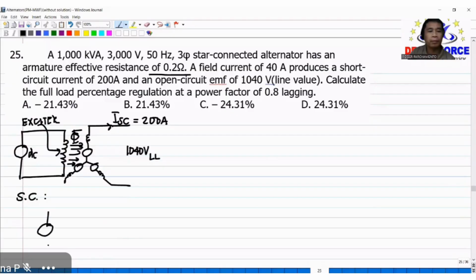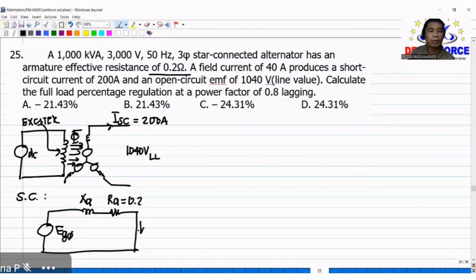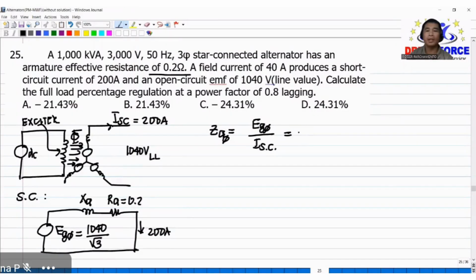So we have ito yung no load or EG per phase. Then nandito naman yung impedance. So XA, yan, ito yung R, A, 0.2. Short circuit, 200 amperes. Then EG per phase is 1040 divided by square root of 3. Okay. So what is the impedance of the armature per phase? So Ohm's law, EG per phase divided by the short circuit current. EG per phase 1040 divided by square root of 3. So that is a Y connected or star connected. Then divided by 200 is 3 ohms.